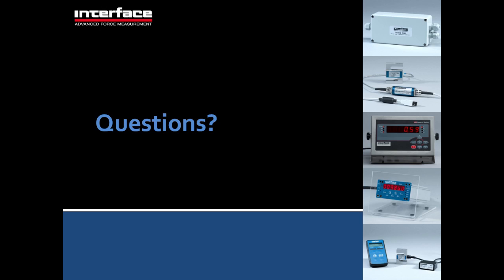Is there a way to verify my 9860 indicator is scaled properly in the field? Yes, as Keith mentioned earlier, he talked in detail about the shunt cal or RCal function on the 9860 indicator. Basically, what that does is it's simulating a load, taking the load cell out of the circuit and putting a resistor in the circuit. So that's a known load. And on the 9860, we've got a button on the front where you press that RCal button.